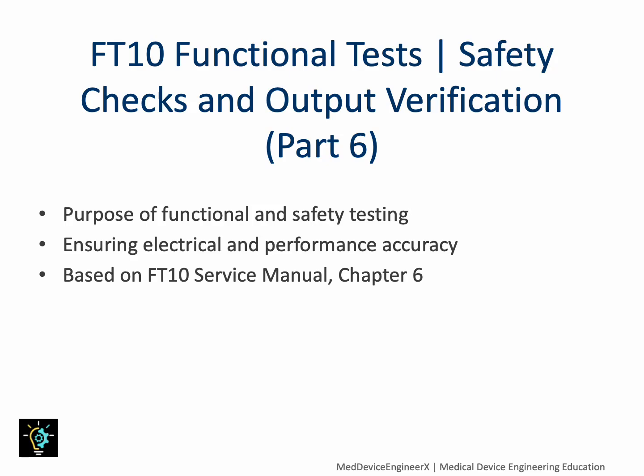In this session, we'll review how to verify that the Valleylab FT10 generator performs safely and accurately after service or during routine maintenance. The goal is simple: confirm that every output, alarm, and circuit behaves as designed. We'll follow the procedures from Chapter 6 of the Service Manual, focusing on inspection, power verification, and leakage checks. By the end, you should understand how to confirm electrical safety to IEC standards and ensure the generator delivers precise power for clinical reliability.